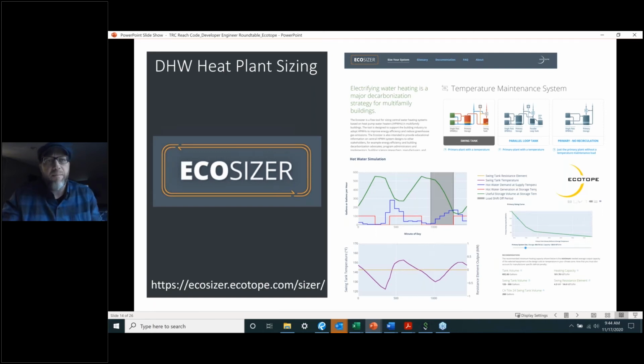Next piece would be the heat plant sizing. Ecotope, along with Southern Cal Edison and SMUD, developed an EcoSizer program, designed specifically to size central heat pump water heating systems. What you'll need are a number of units, number of occupants, and some information about the type of plant you're planning your system around. This system can do hot water simulation and sizing, with some variability so you can tweak it, designed around the designer.